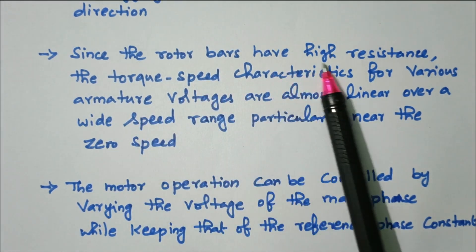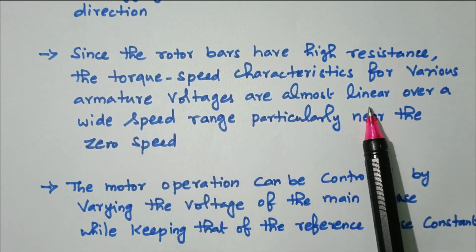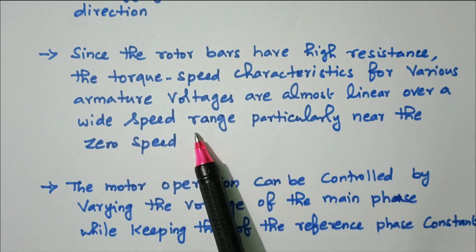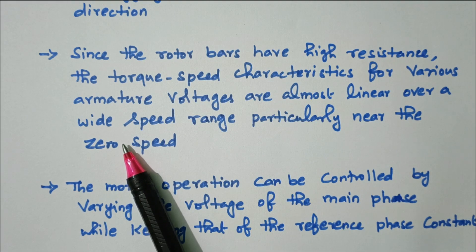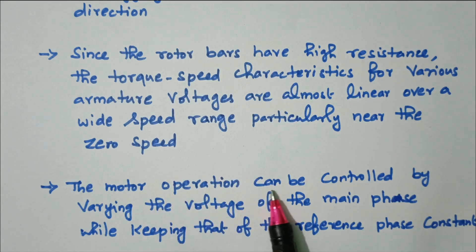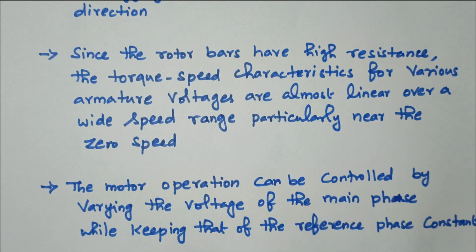Since the rotor bars have high resistance, the speed-torque characteristics for various armature voltages are almost linear with a negative slope over a wide speed range, particularly near zero speed. So when speed changes, torque also changes linearly. The motor operation can be controlled by varying the voltage of the main phase while keeping the reference phase voltage constant. That covers the two-phase AC servo motor.